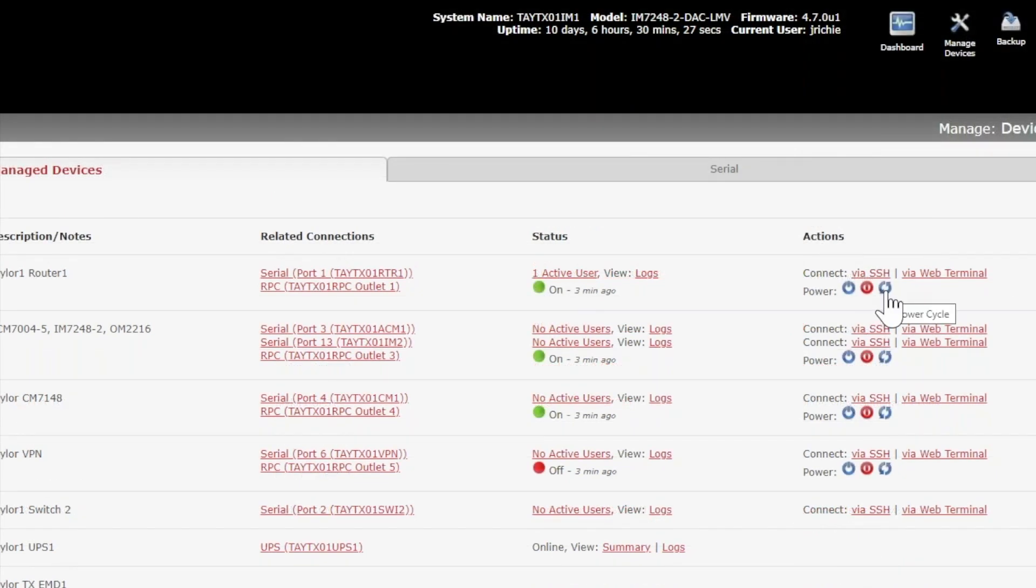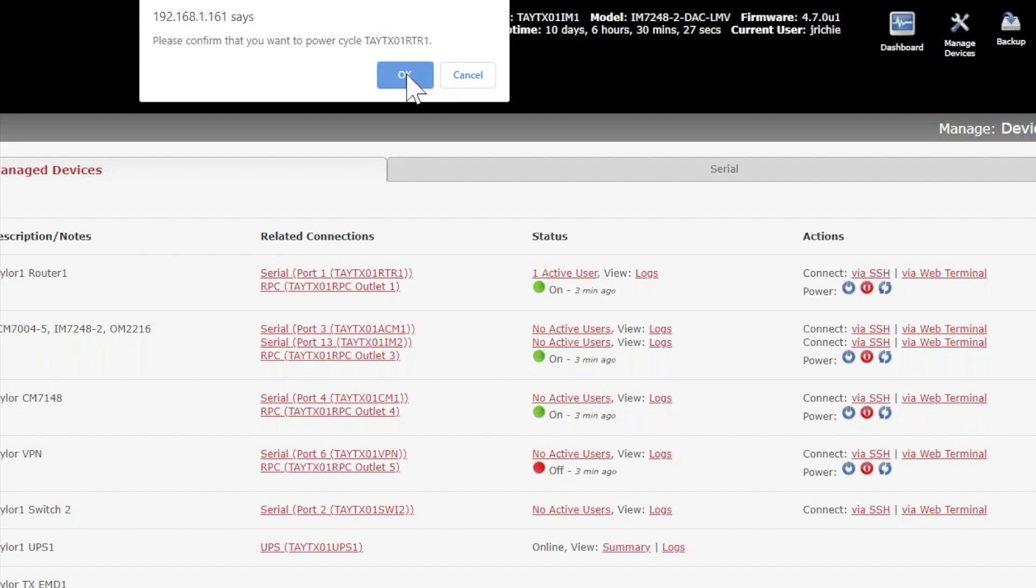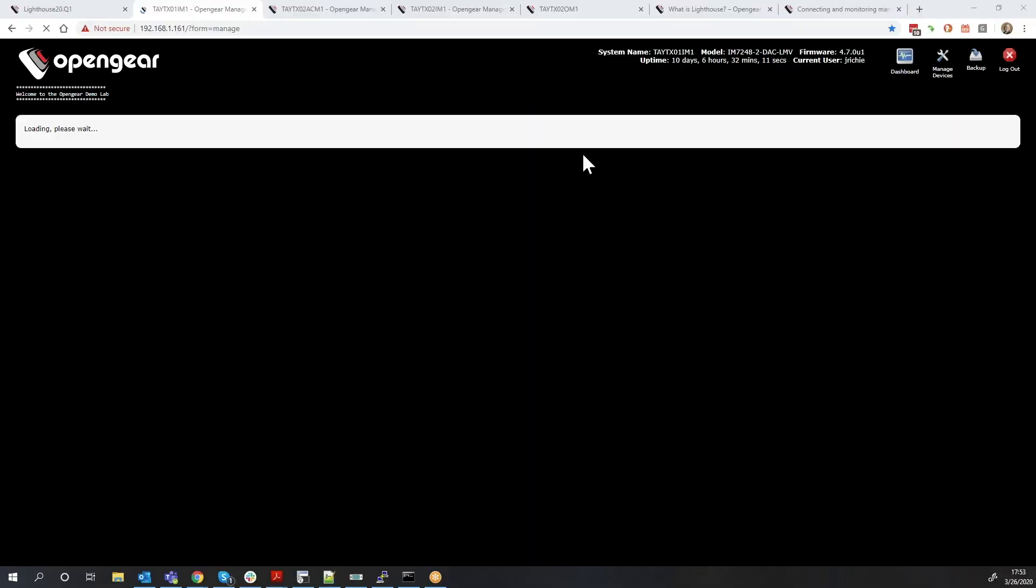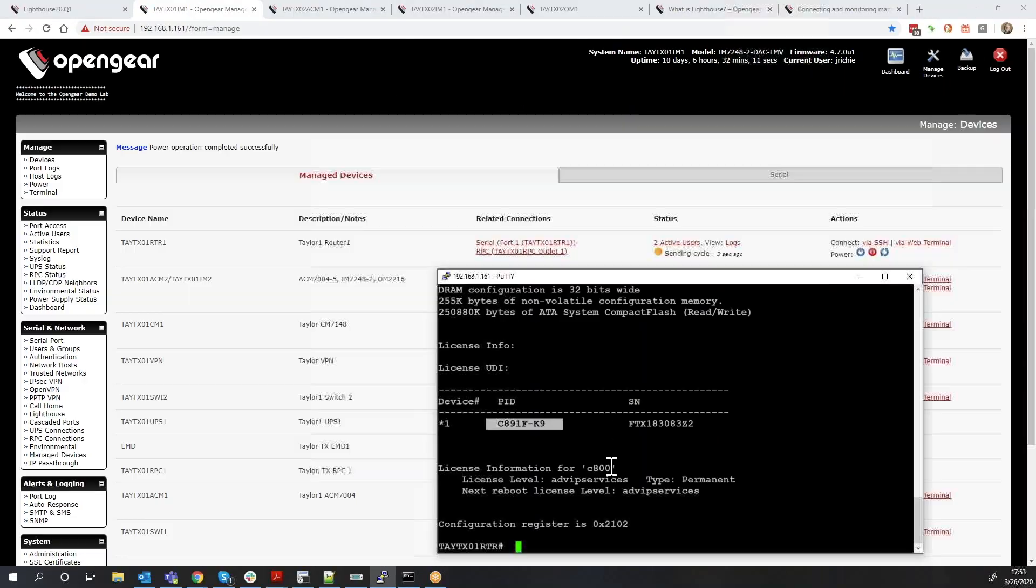That's what I'm gonna do right here. I'm gonna issue the power cycle. I just click this little button, confirm that yes, in fact, I want to power cycle this device. And then we'll see over here the OpenGear in the background is sending the command to this remote power controller. It's saying shut off outlet number one and then turn it back on.